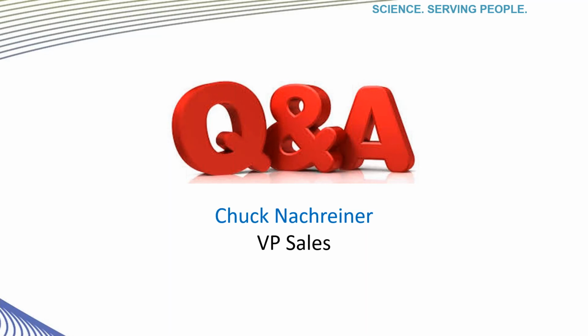Question from James: is ultra low flow mode needed for sampling low flow rates? Yes. Anything below 500 mils a minute, you need what we consider to be an all-in-one or a CPC and an adjustable low flow holder. That basically puts the pump in constant pressure mode and allows you to run more than one sorbent tube at a time. You're delivering a constant pressure to an orifice, and then there's a needle valve in the all-in-one and the adjustable low flow holders that you change to make flow adjustments.